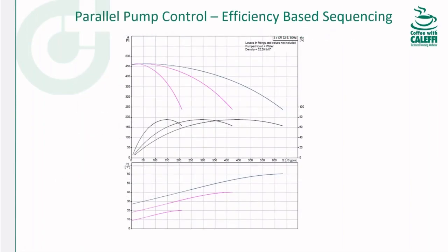Okay, so here's a pump curve for the triplex system with three pumps in parallel. These dark shaded lines are one pump running. On the top, that's the pump curve. The middle is the efficiency, and the bottom is the brake horsepower. And then we have the same thing for two pumps, and the same thing for three pumps. What we want to do here is basically trace the line at the highest point across the full flow range. So whatever our flow is, let's say 600 GPM, this is the highest point.